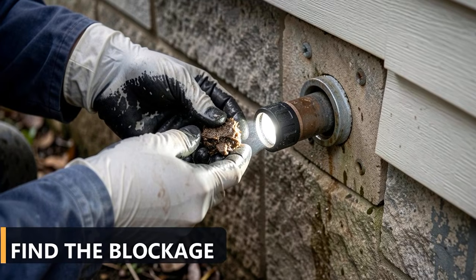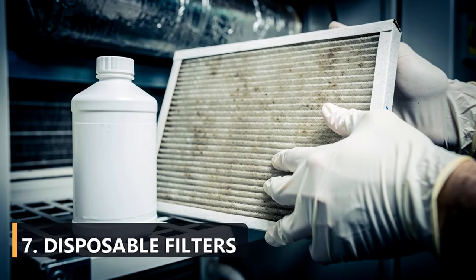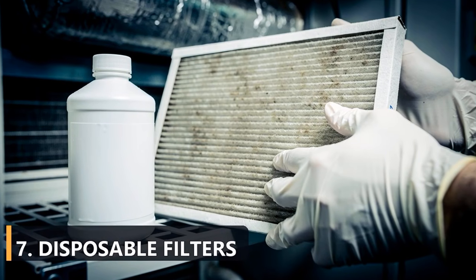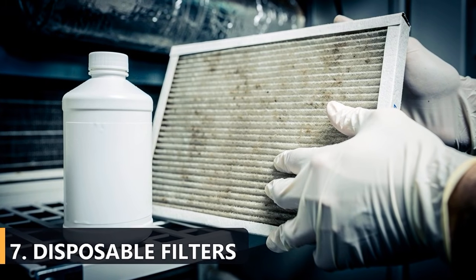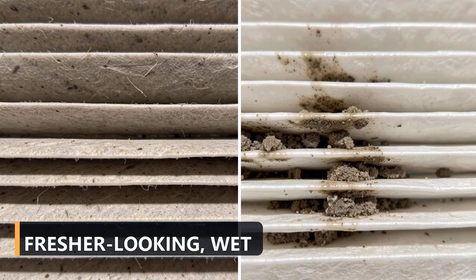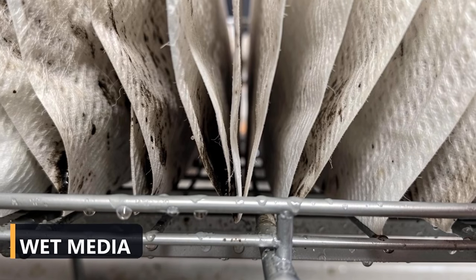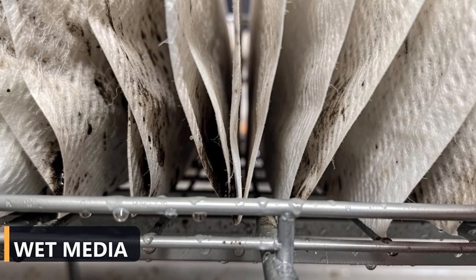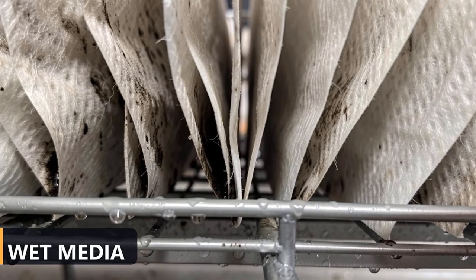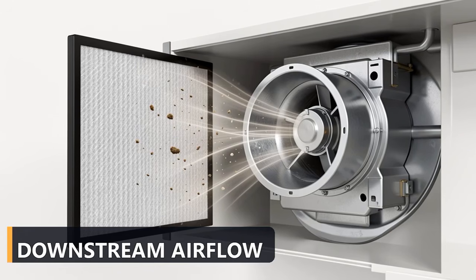Number 7. A disposable air filter should not become a peroxide sponge. A dirty pleated filter can appear gray, stained, or even spotted. Spraying it with peroxide may make the surface look fresher, but it also turns captured dust into wet material. Moisture can weaken the filter media, disturb its structure, increase resistance, and create a damp object directly in the airflow. When the fan starts, loosened particles or droplets may move downstream toward the blower and coil.